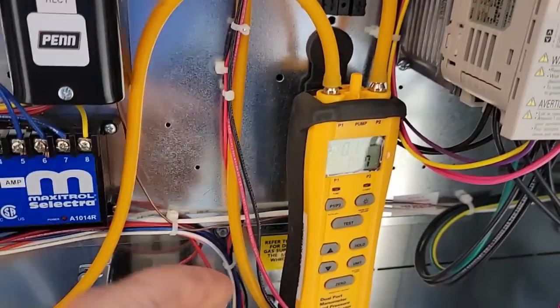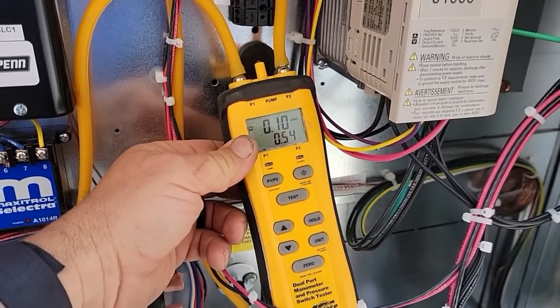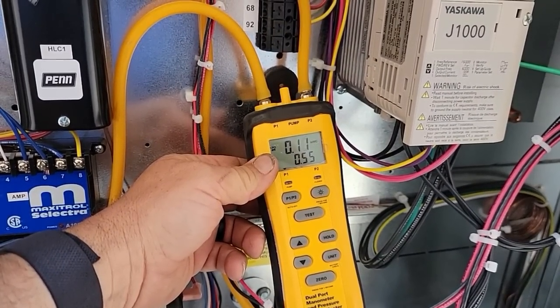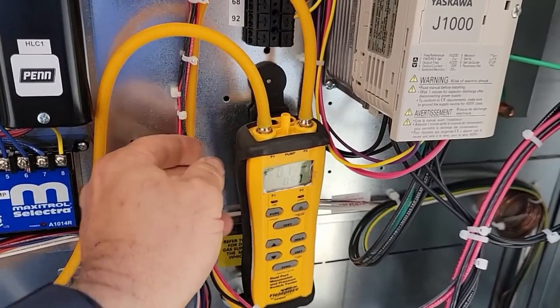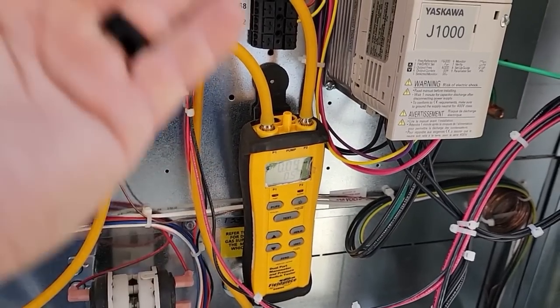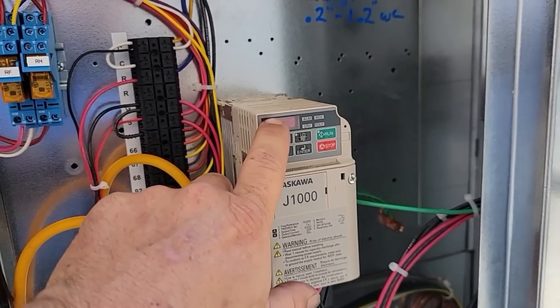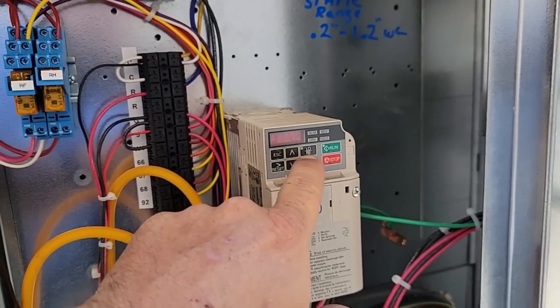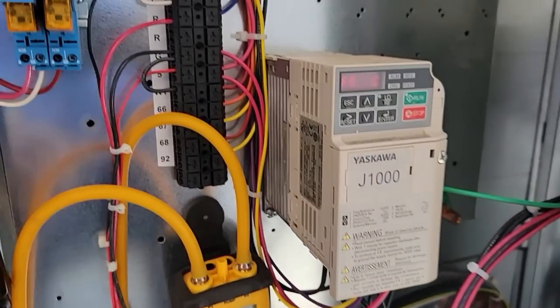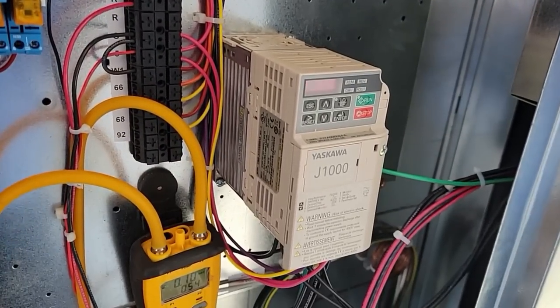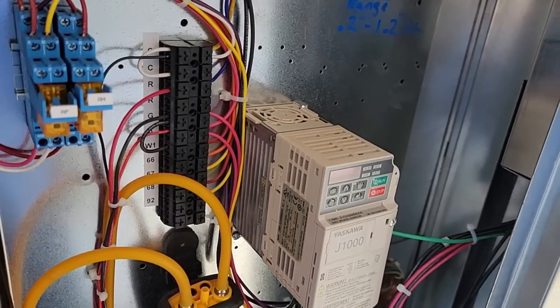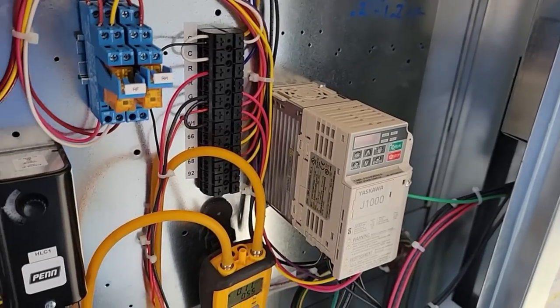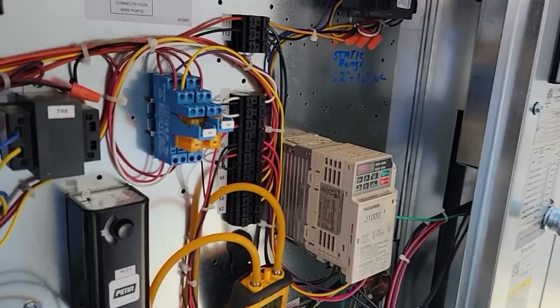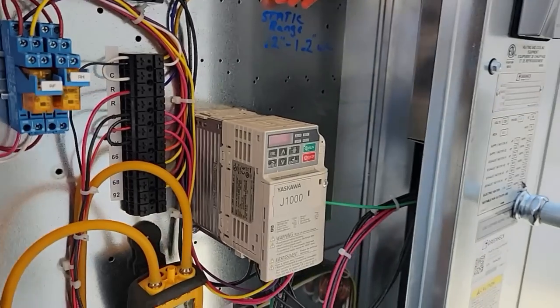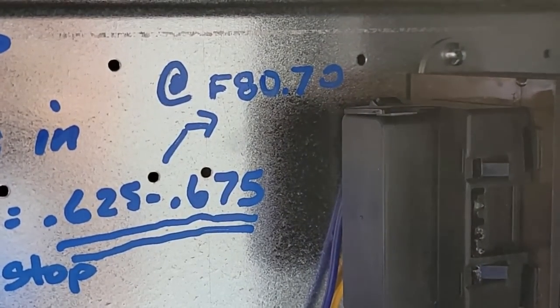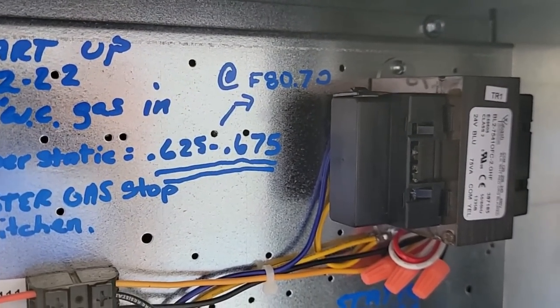Now our static pressure has changed a little bit, but like I said, we need a minimum of 0.2, so we're well above it. So even because of this weather, we're good. I am going to mark that this was at frequency 80.7. That's as high as I can go with it. Here, that way we know what we had when I had it at that particular setting. If somebody else comes along later and changes it, then they're like, no, you never had that before. And it's like, well, that was at that particular frequency, because obviously slowing down is going to change it. There we go. So we got a little documentation there.